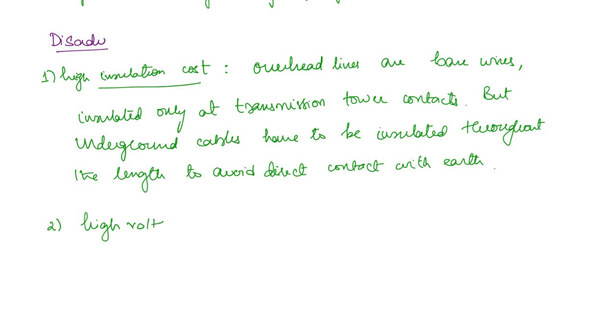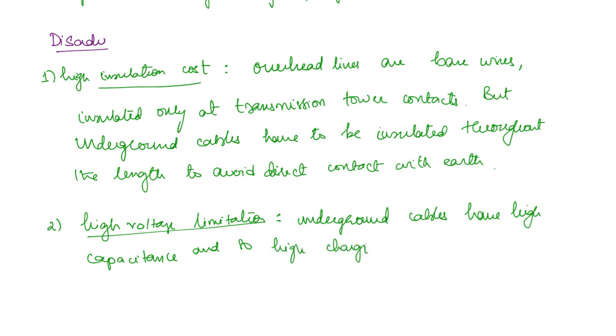The next disadvantage is there is a limitation to the voltage level. Why is that? It is because of the capacitance. Underground cables are associated with more capacitance, and when there is more capacitance there will be more charging current. Charging current increases with voltage, so we have a limitation on the voltage level that can be transmitted. Underground cables have high capacitance and high charging current, which limits the use of cables for high voltage levels.